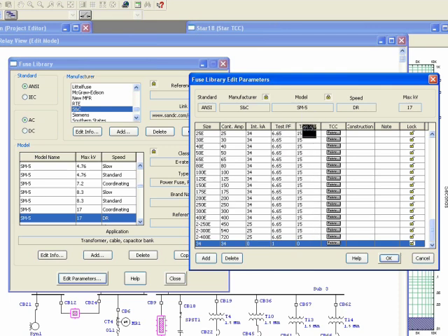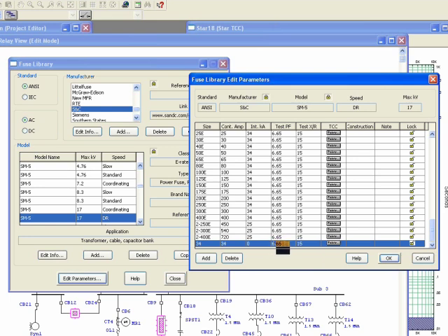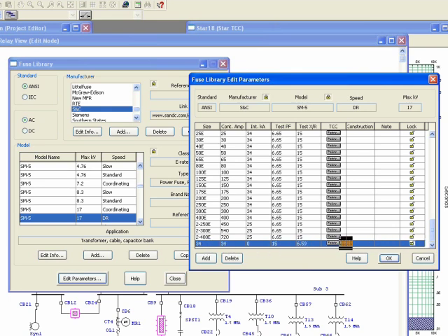There are fields for test power factor and test X/R ratio, which are automatically calculated. For example, if a fuse is tested at 15 X/R or a test power factor of 6.65 per the manufacturer data, you can specify that here. Entering the test power factor will automatically calculate the test X/R for you. Construction and notes are additional fields where you can enter more information related to that fuse.